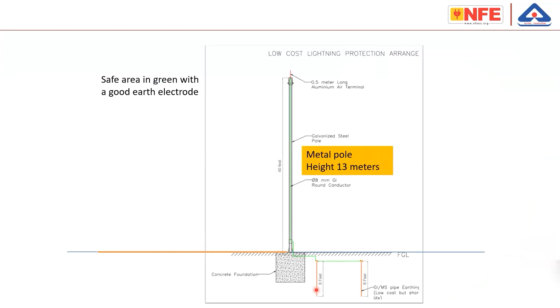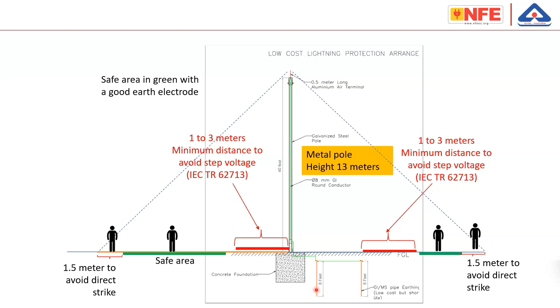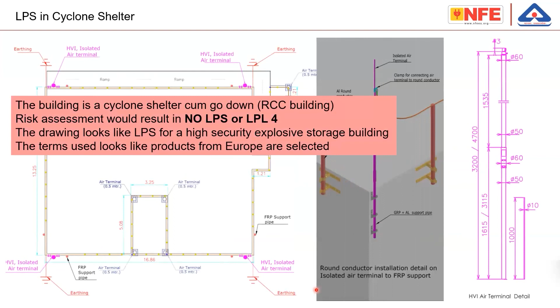Even if we think that there is a very good earth electrode and the distance from the pipe is not 10 meters, let us say 1 to 3 meters, even then the actual protected place is quite small. It is not like the entire 45-degree shadow area is protected. So please understand such dangers and educate the people properly so that they are not fooled because of this foolish education happening in India. Similarly, it was claimed that hundreds of cyclone shelters across India are protected with lightning protection.